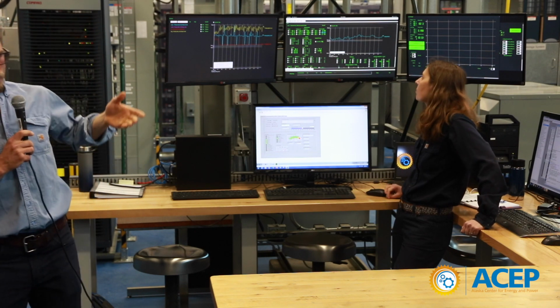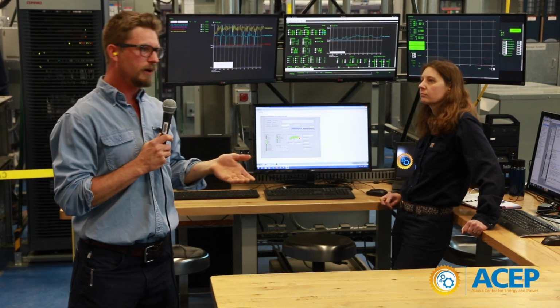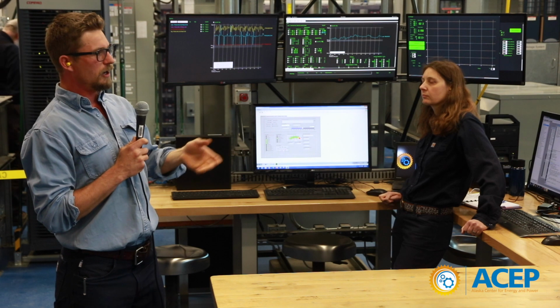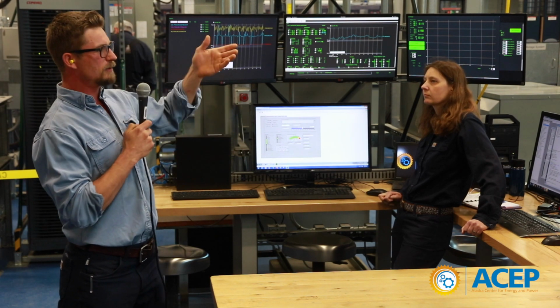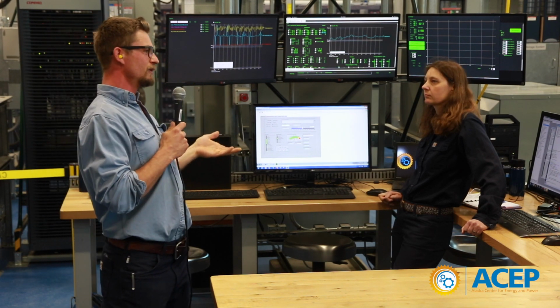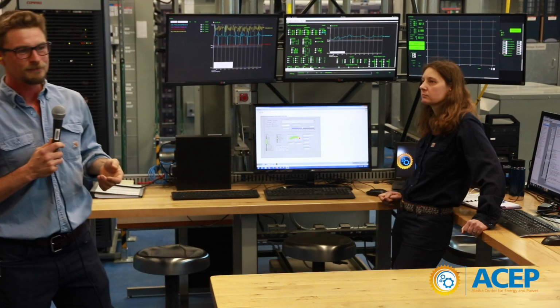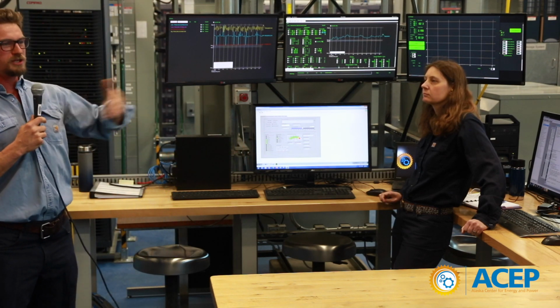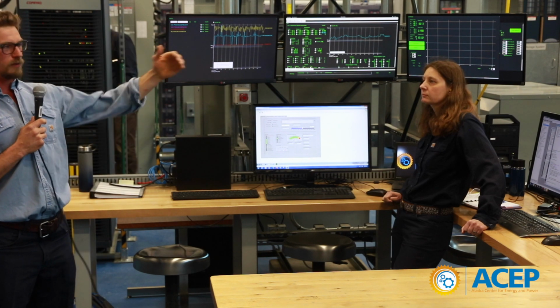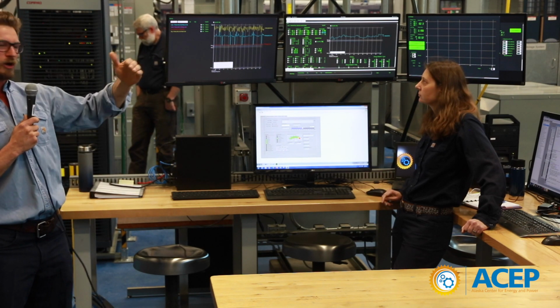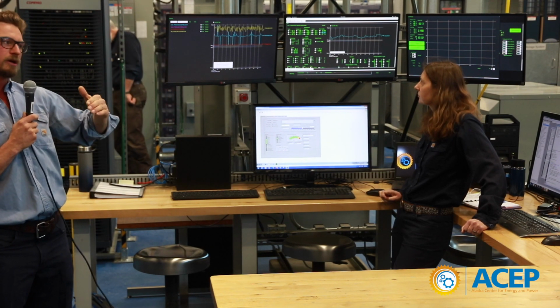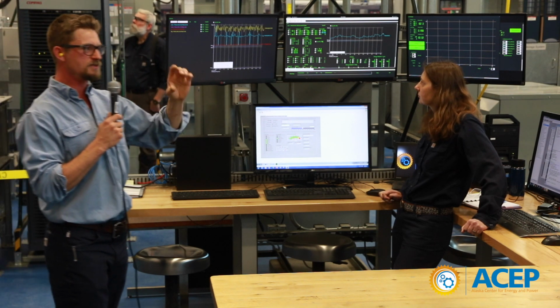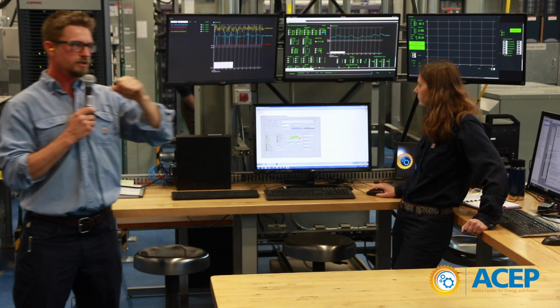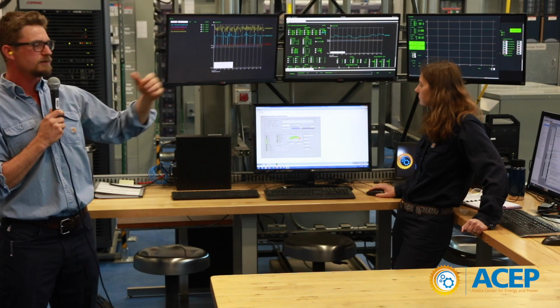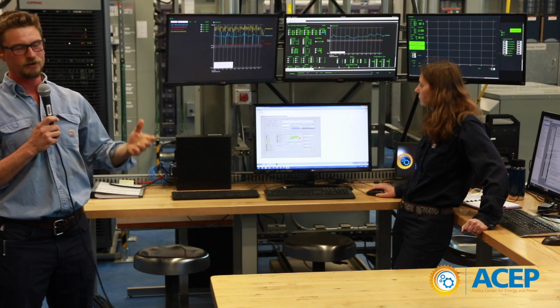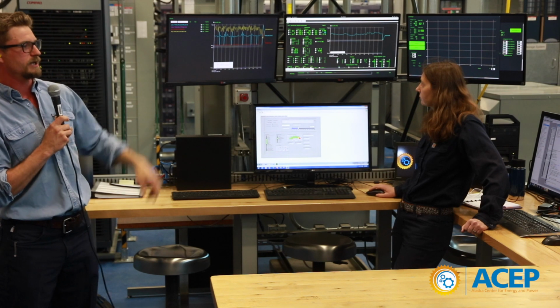Also, now we have 100 kilowatts of installed wind power on our grid, where our maximum load is about 100 kilowatts. So what's going to happen? We're going to curtail a lot more wind, right? We have to rein back that wind because we can't let it get close to low loading our diesel. We have to keep 30% on our diesel. So we're using a lot more of our wind power as heat, or worst case scenario, we're just dumping it. We're just not using it.